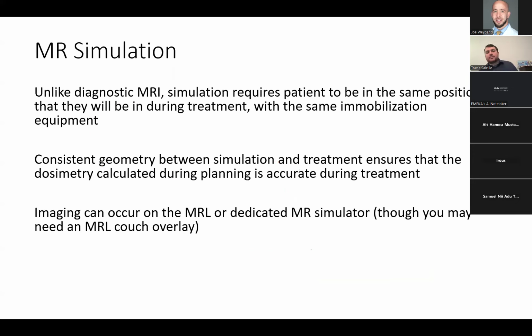From the MR simulation point of view, unlike diagnostic MRI, the simulation requires the patient to be in the same position that they'll be during treatment. So we use the exact same immobilization equipment that will be used during treatment. This is something to consider because there's immobilization equipment that we do for CT simulation that utilizes some types of metal that we don't want to bring into the MRI, both from a ferromagnetic point of view, but also an image quality point of view. So your equipment might have to change, for example, from carbon fiber to like a plexiglass material.